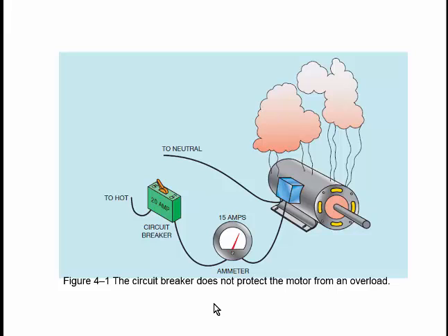Circuit breakers don't protect the motor from an overload. The circuit breaker is set high so that the motor can start. When a motor starts, there's a lot of current flowing, so we have to install a circuit breaker that's kind of big. Then the overload is set small, but it has a long time delay, so that short duration motor starting doesn't trip the overload. The overload only trips when you have a lot of current. So in this example, we have 15 amps flowing, the motor's overheating, the circuit breaker is not tripping. Hopefully there's an overload in here that will trip.